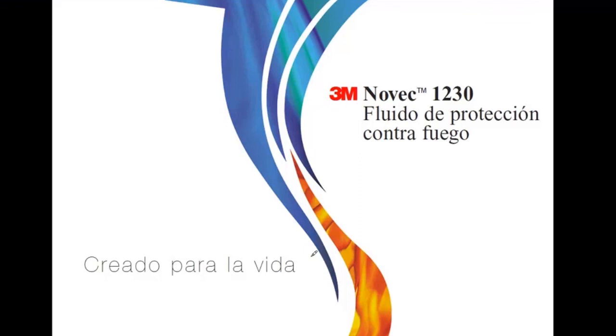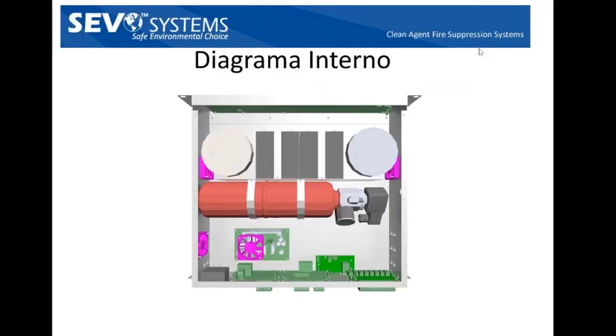And in case of fire, the electronic sends a command, a remote command, so everybody is notified about this situation via IP, but also locally with open and closed contacts that can be connected to the building fire alarm or the DBMS of the building. And obviously, it has enough Novec to protect the space I am mentioning, a regular full rack 42 units.